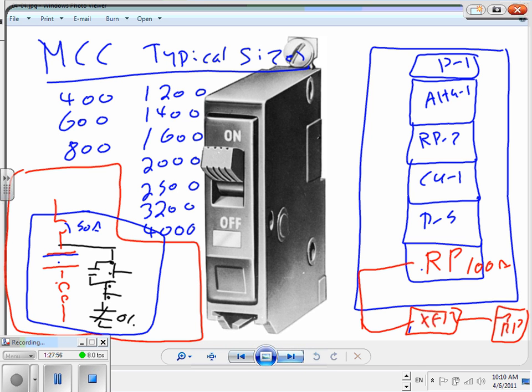The only thing you need to understand in this article, guys, is, number one, you have to have an overcurrent protection device for every panel. That could be inside the panel or outside the panel. And the overcurrent protection device has to match the panel or be smaller. It cannot be more than what the panel is rated for. So that's basic, and a couple of things about structure, how to build it. If you have space openings in the panel, you have to cover them. For example, if you have a slot that's not used in the panel, the code says you have to cover this slot with a steel cover equivalent to the steel structure of the panel. But it doesn't tell you how to size them in any NEC code book, nothing.